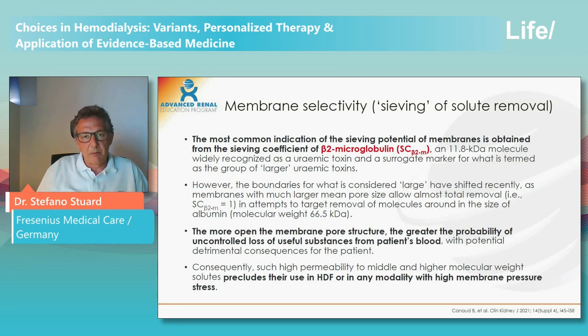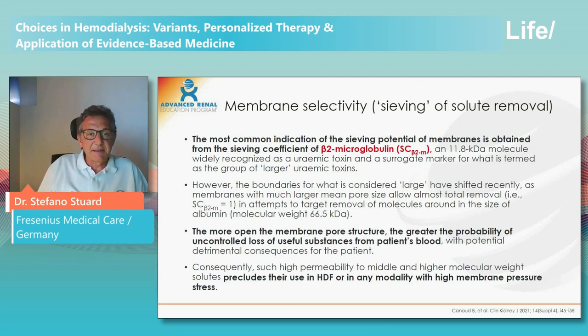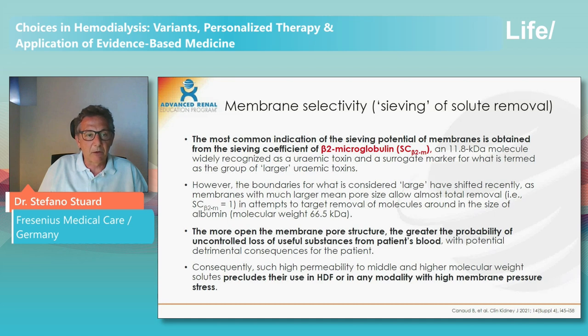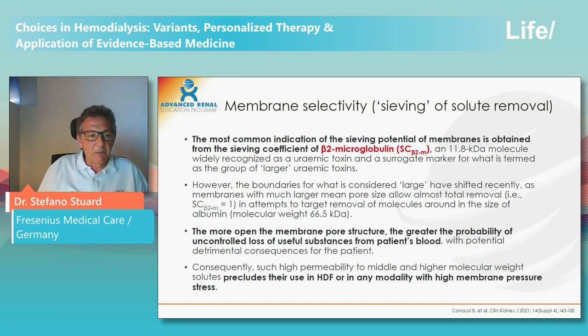Normally a dialyzer should have a sieving coefficient for beta-2 microglobulin equal to one. However, it is important to recognize the risk of removing substances that should not be removed — I am referring mainly to albumin. The more open the membrane pore structure, the greater the probability of uncontrolled loss of useful substances from the patient's blood, such as albumin. Consequently, such permeability to middle and higher molecular weight solutes precludes their use in hemodiafiltration or any modality with high membrane pressure stress.